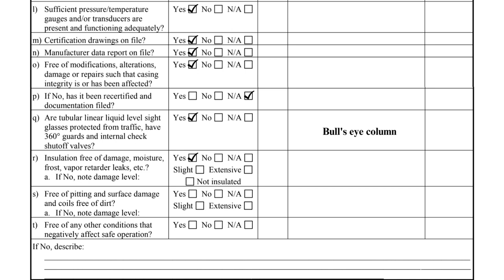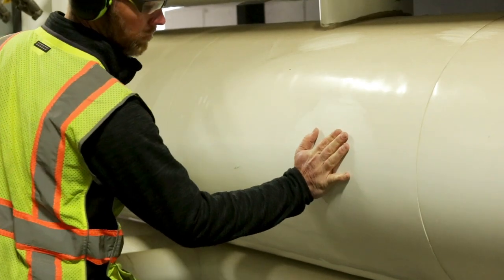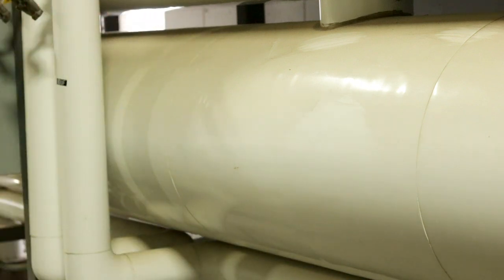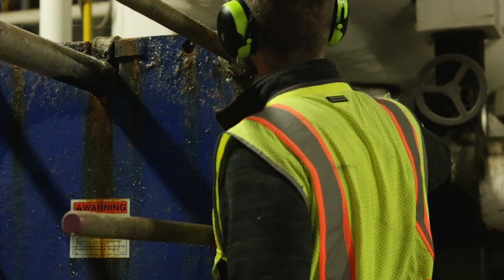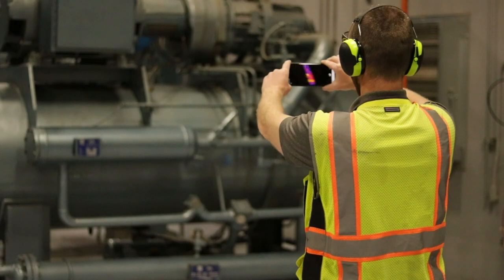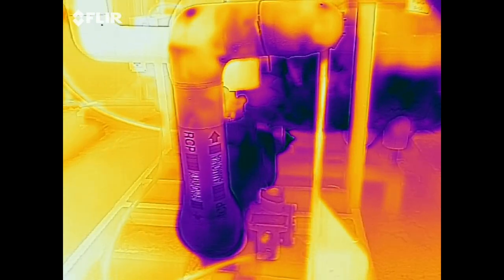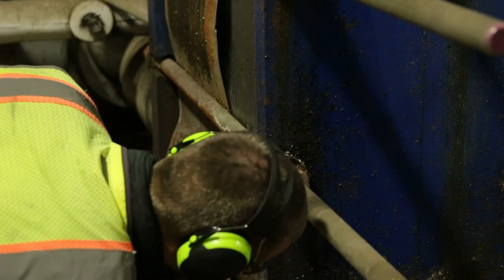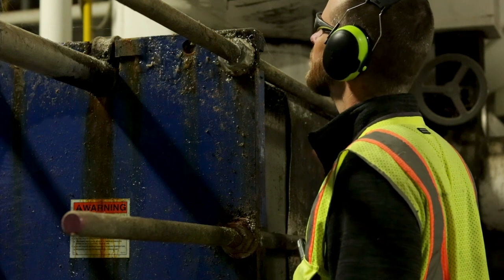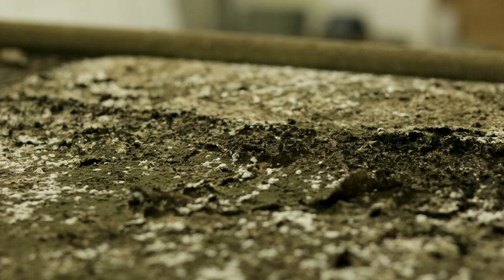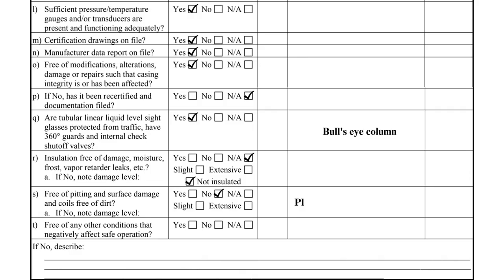When a heat exchanger is insulated, the insulation system must be inspected per Item R. Deficiencies such as jacket damage, breached vapor barrier, and ice buildup must be noted. This glycol heat exchanger is not insulated, so NA and not insulated should be checked. A thermal imaging camera can be helpful to identify insulation system failures that cannot be observed with the naked eye. For non-insulated heat exchangers like this one, Item S requires the entire surface of the heat exchanger to be inspected, and any surface corrosion or pitting must be recorded as a deficiency. This plate and frame heat exchanger has excessive dirt and debris on the top of the unit that requires corrective measures.